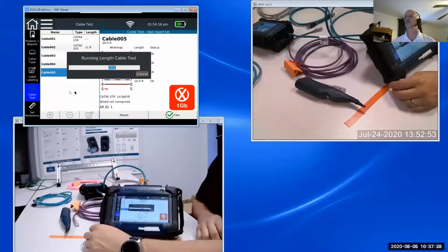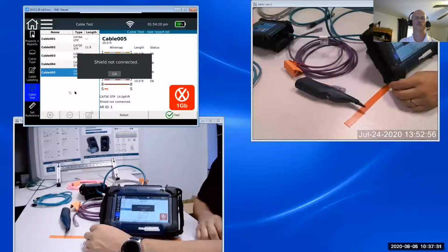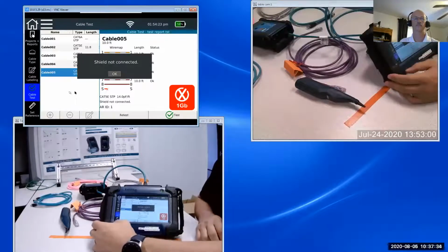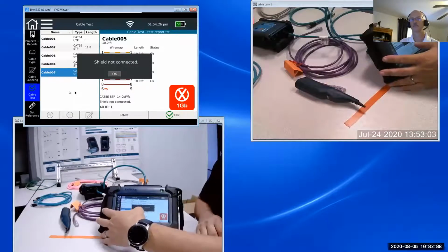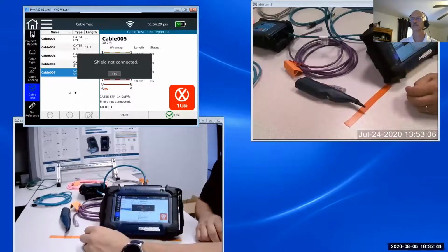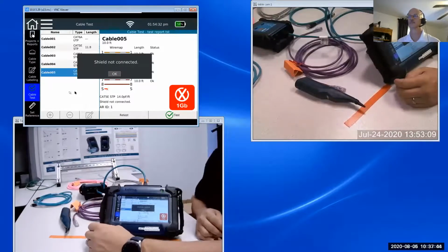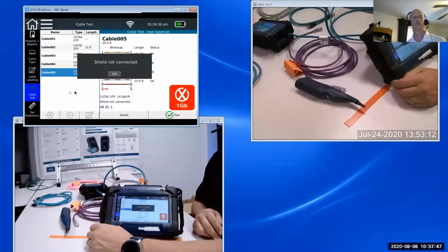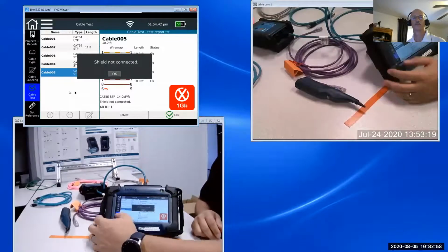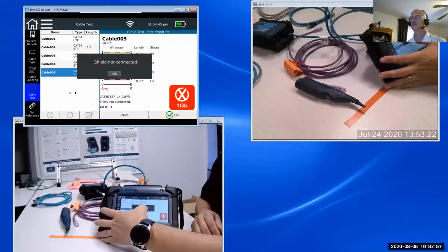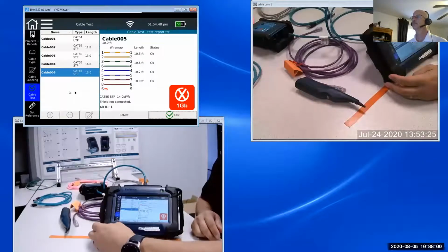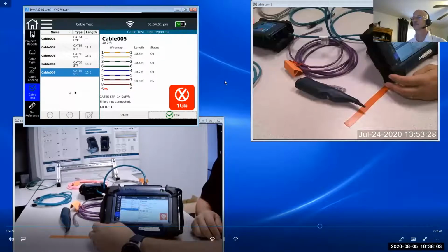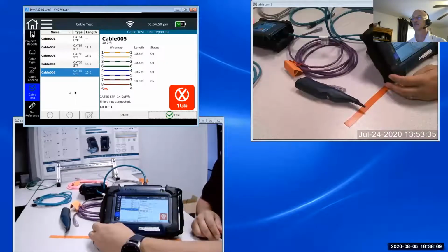It's then going to move on to running the additional tests. Right out of the gate, it tells us that there is not a correctly terminated shield on this cable. So it's failing our test because we set this up to test for shield. Now you can set up the XG to ignore the shield or to test cables that do not have a shield, but in this instance we do want to have a shield, and this cable does not have a properly connected shield, so it fails. I do get the length of each pair and the overall length of the cable, but again, no shield on this cable, and because of that, it has failed.